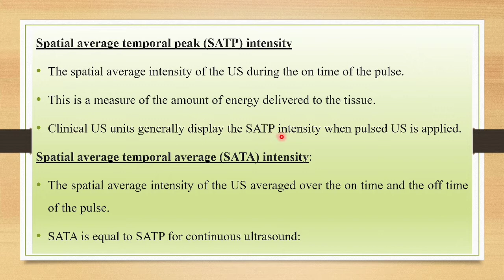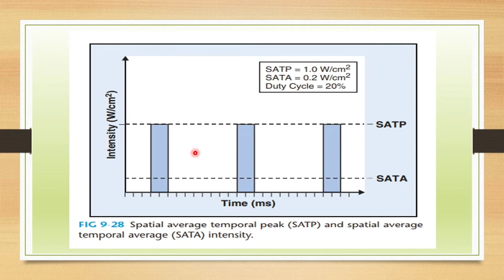And the next parameter is your spatial average temporal average intensity. This is the spatial average intensity of the ultrasound averaged over the on time and off time of the pulse. So spatial average temporal average intensity is equal to spatial average temporal peak intensity for continuous ultrasound. For pulsed ultrasound, the spatial average temporal peak intensity is different. This is the diagrammatic representation of the spatial average temporal peak intensity and spatial average temporal average intensity.